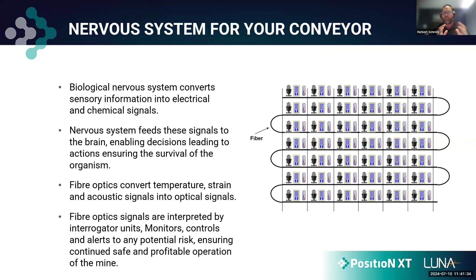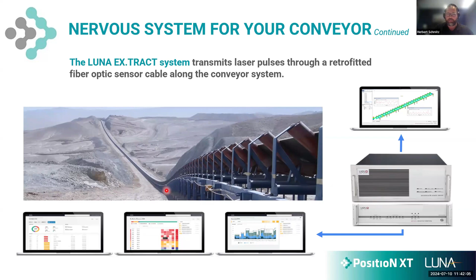So within this slide, what we would have is the fiber optic cable running all along the conveyor infrastructure for the entire length thereof on either side, connected to our interrogator unit, which in turn interrogates one for the condition monitoring, the vibration along the conveyor, as well as the temperature system to do the temperature side. The heart of this system is our sensor cable. The fiber optic cable is the sensing instrument. There's nothing else connected to it. The cable itself is the sensor.